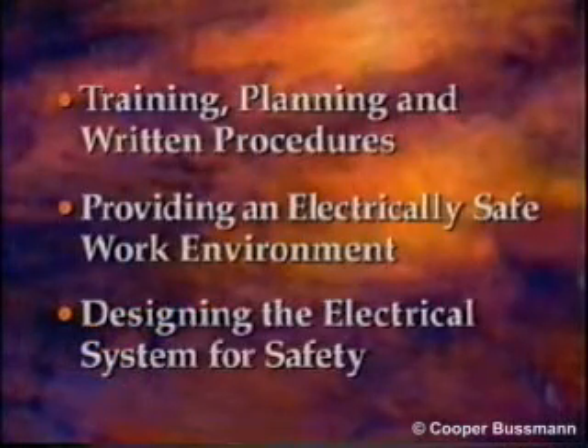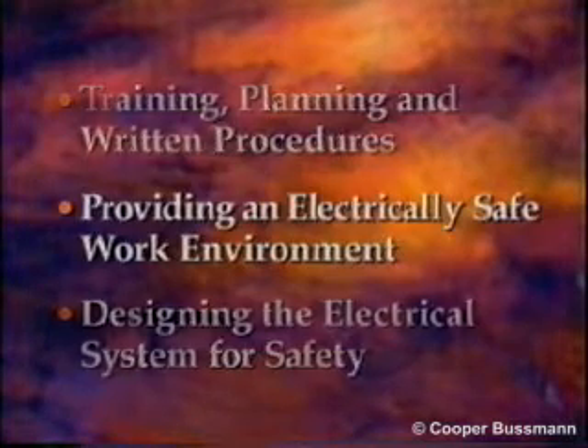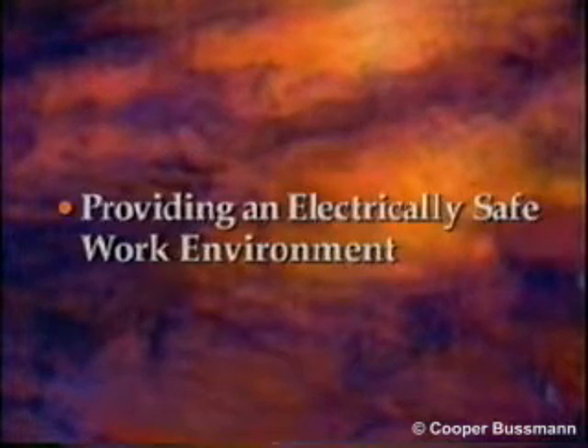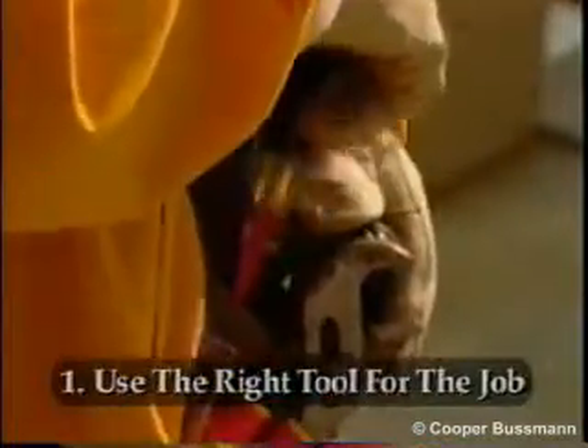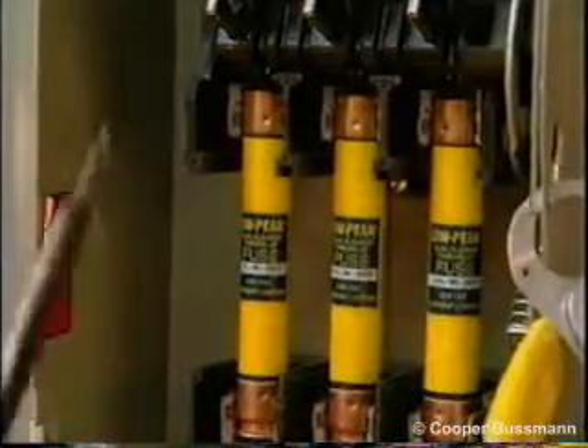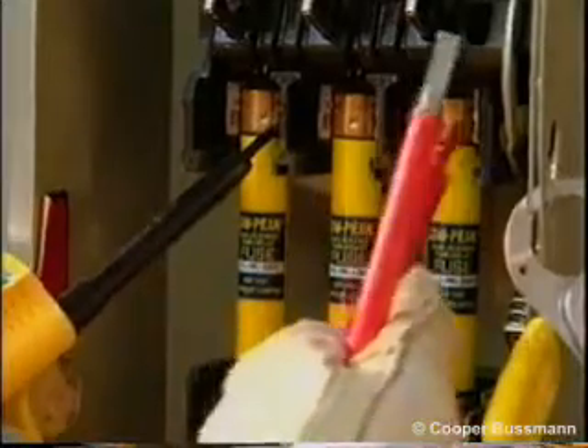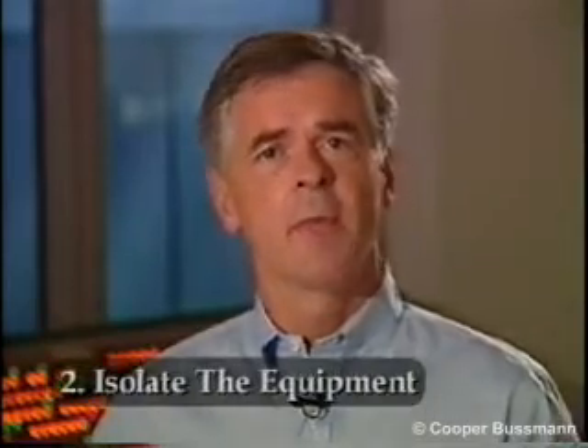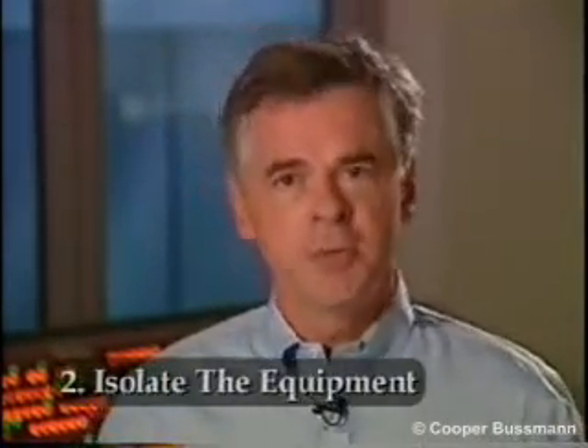There are also a number of principles that apply to the second focus area, providing an electrically safe work environment. Use the right tool for the job. Use the appropriate tools for the job at hand. Keep them accessible and in good working condition. Using a screwdriver for a job that requires fuse pullers is an invitation to an accident. Isolate the equipment. The best way to avoid an accident is to reduce exposure to hazards. Keep doors closed. Keep barricades in place. Install temporary voltage-rated blankets covering exposed live parts.